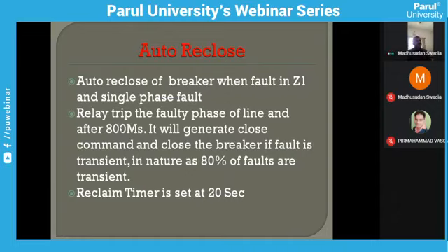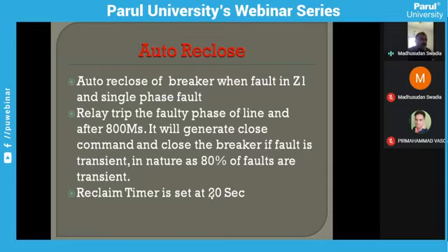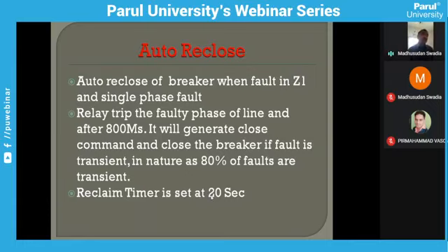The significance of the reclaim timer is as follows: suppose a line trips and recloses and the line is restored, but before 20 seconds (the reclaim time) elapses, the same tree comes near the conductor again. In that case, the autoreclose will not take another chance to reclose — because if it continuously recloses while the fault keeps coming, it would continuously try to reclose. The reclaim timer ensures the autoreclose only operates once within a set time window, protecting the system from repeated reclose attempts during persistent or recurring fault conditions.